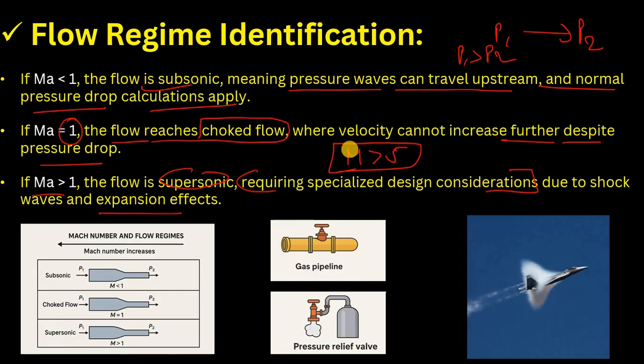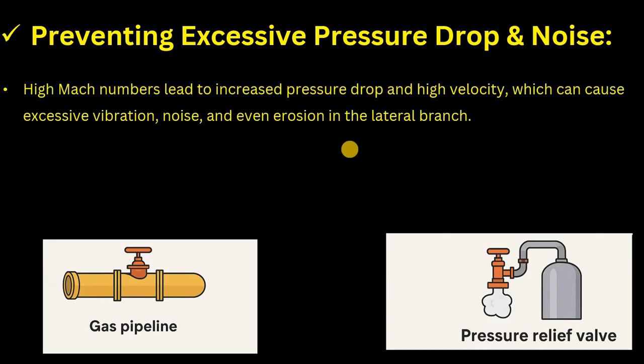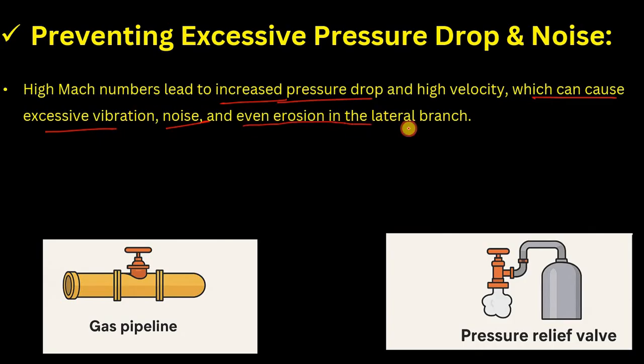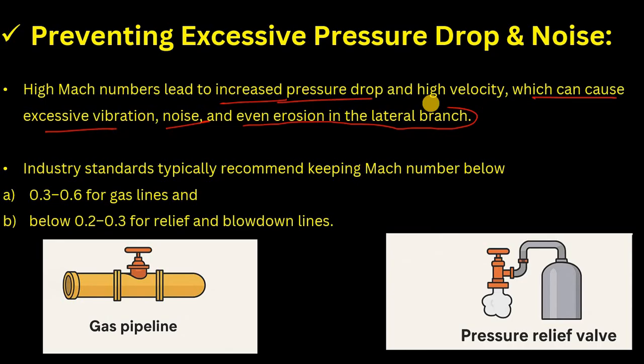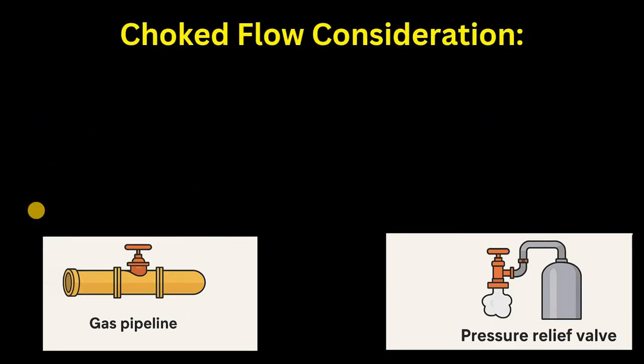High Mach numbers increase velocity and pressure drop, causing excessive vibration, noise, and even erosion in the lateral branch — all potentially leading to mechanical failure. For industry standards, gas lines typically keep Mach number between 0.3 and 0.7, while relief lines and blowdown lines typically keep it below 0.2 to 0.3.